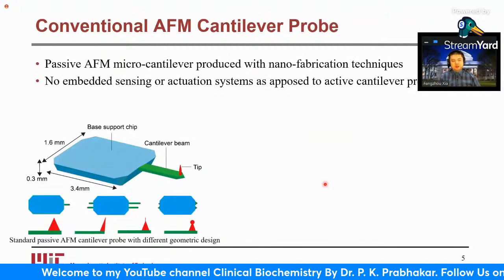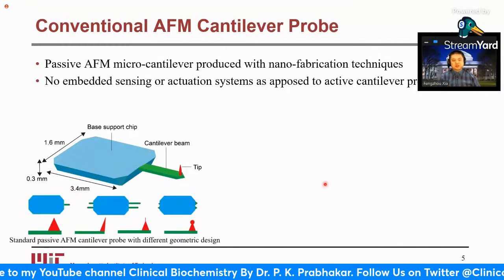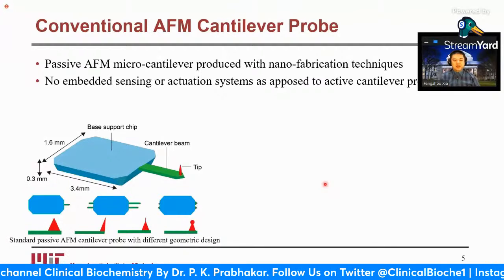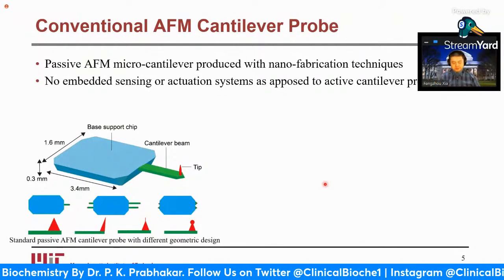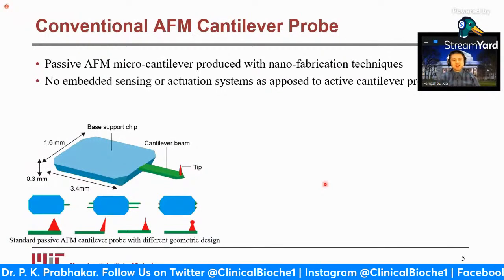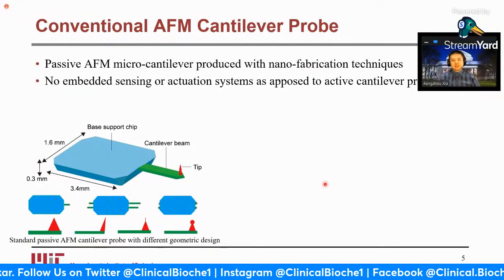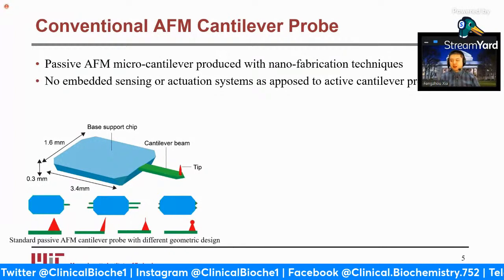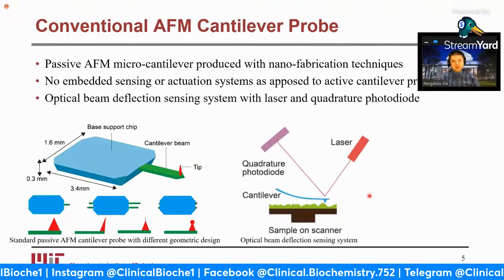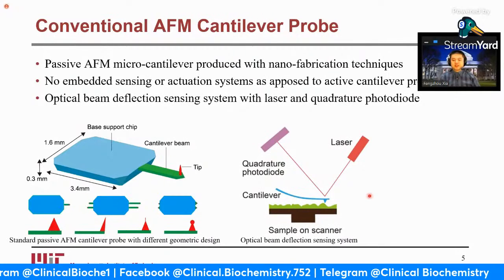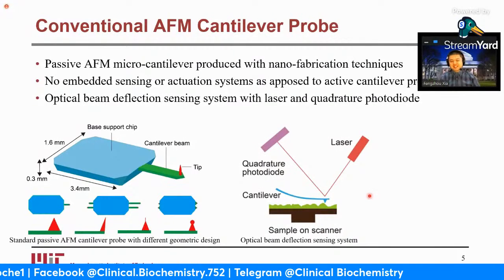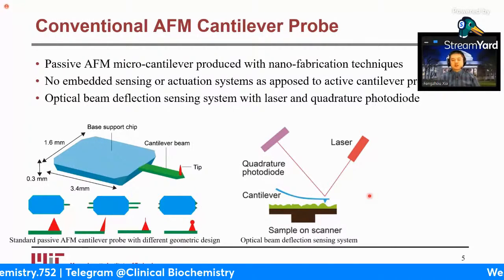For the probe, we start with the passive ones, which usually do not have any MEMS components embedded on top of them, so that the deflection is usually measured by the optical beam deflection sensor. Experienced users of the system will be quite familiar with this process. You first need to align the laser to the cantilever and then adjust the quadrant photodiode so that you can get the signal at the center of it.